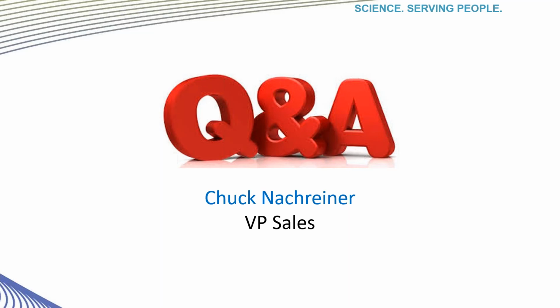Another question from James: is the Checkmate a primary standard? We have recently gotten away from the terminology primary, and we refer to it as calibrated to a NIST standard. The Checkmate is a 1% instrument, so over the full range, it's at 1%. We've been very successful in selling these to the compliance bodies that are out there. So if you look at it in the way we used to, the terminology for old calibrators, this would be considered a primary, but we are now referring to it as a 1% instrument calibrated to a NIST standard.